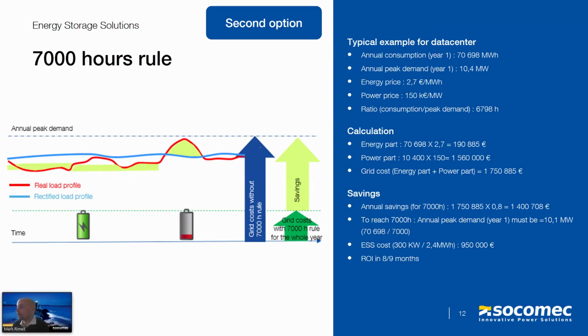If, however, we could increase that and flatten that profile so that we can achieve a 7,000 hour rule, we could benefit from a saving of €1.4 million based on saving 80% of the grid costs. So in order to reach 7,000 hours, you can see their peak demand must not exceed 10.1 megawatts. That would be their 70,000 megawatt hour consumption divided by 7,000 gives us the 10.1 megawatts. The gap here is 300 kilowatts.